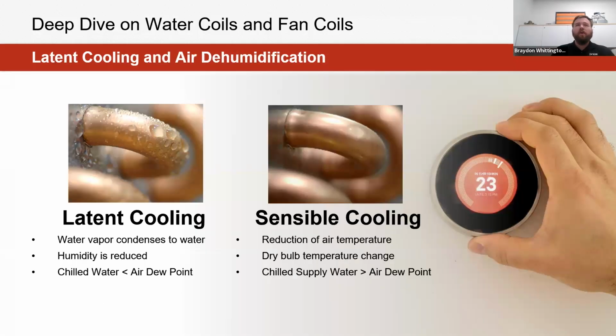We mentioned cooling coils, and that's a key parameter that really distinguishes terminals from fan coil and blower coil equipment. The reason for that, and how it's different from these VAV systems, is that it's also handling latent cooling. So those wet bulb temperatures, or reduction of humidity, or condensation that's going to be happening in our system. You're now having entering temperatures through these cooling coils that are below the dew point. So when we mentioned that all these products come with a drain pan, the reason is that there is going to be some condensation happening at that coil. That's just a means of mitigating that when we're trying to adjust for some of the humidity control going through it.